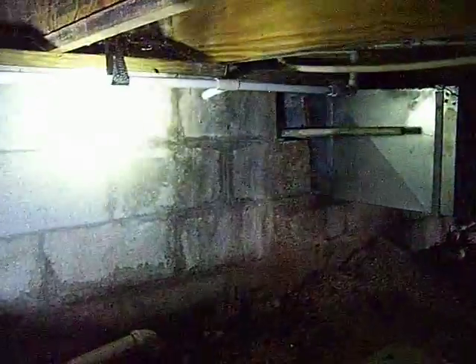So we're down in the crawlspace. The condensate line, I believe, is what this is, coming off the AC unit. And you can see that it's open here — they didn't cap off where this T is, and it's just dripping down in the crawlspace, creating a very damp area. Quite a mess. So that needs to be corrected.